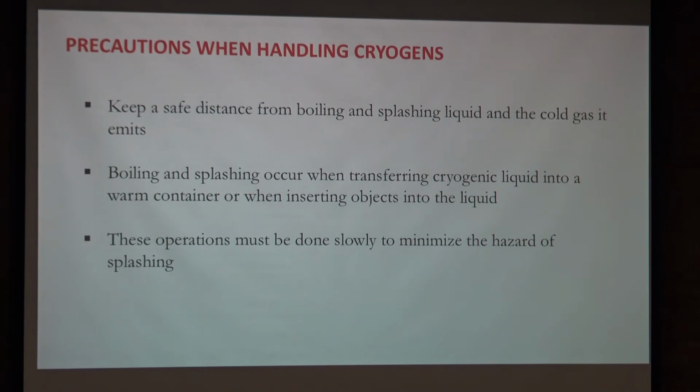If you're handling open cryogenic liquids and there is a danger that you could be splashed from boiling liquids, you want to keep a safe distance, obviously. The moment when this becomes most dangerous is if you pour a cold substance like liquid nitrogen into a dewar that starts out at room temperature.